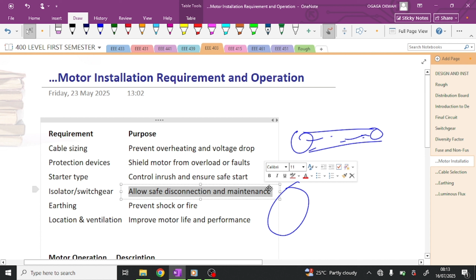Okay, to produce heat. So yes, you have to consider the cable size and the amount of cable, and what the rating is, the current and then the voltage. Consider cable size. Then protective device, to shield the motor from overload or fault. You need to make use of a protective device, like a miniature circuit breaker, switchgear, to shield the motor, so if there's an overload or fault, it will just trip off instead of damaging the motor.